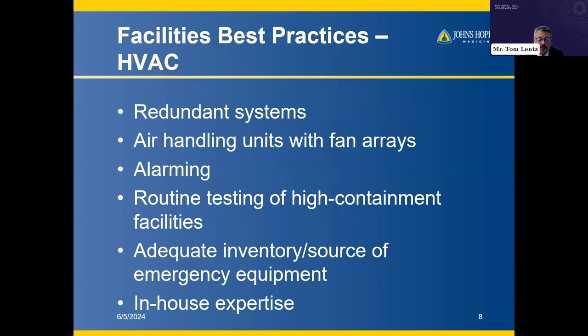Number one is to have as many redundant systems as possible, though there are obviously financial limitations. One example is air handling units with what we call fan arrays. We don't have these everywhere, but our new engineering design principles utilize fan arrays—instead of one giant fan, you have a lot of smaller fans. That gets you to an N+1 or even N+2 situation, so if you lose a single fan it doesn't wreak havoc on the system or create an emergency.